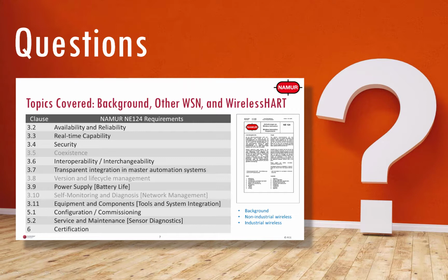Due to cost limitations, would it be recommended to use other cheaper wireless sensor networks, given that integration with existing software is possible? There are two things here. There are a lot of cheaper wireless sensor networks. However, to integrate into existing software, they don't automatically convert into OPC or Modbus, so you would need a system integrator to write scripts and so on to make that happen. At the end of the day, that kind of solution does not become cheaper, because of the additional work to set it up and then maintain it throughout the life of the system. So I wouldn't go that way.